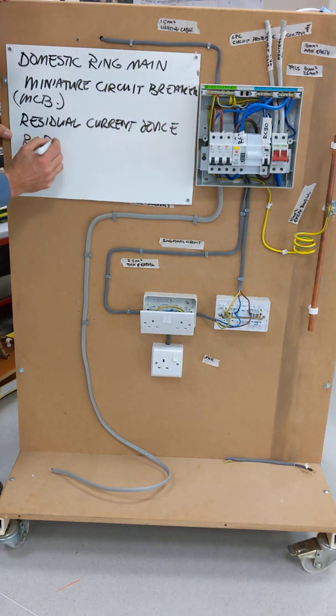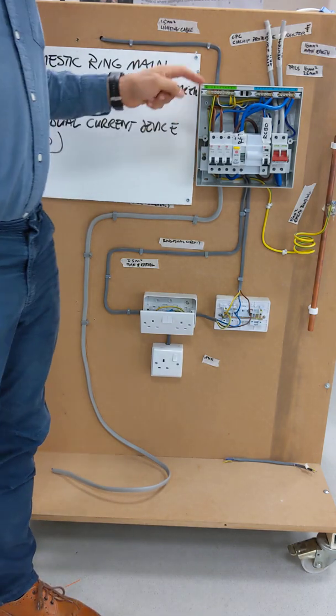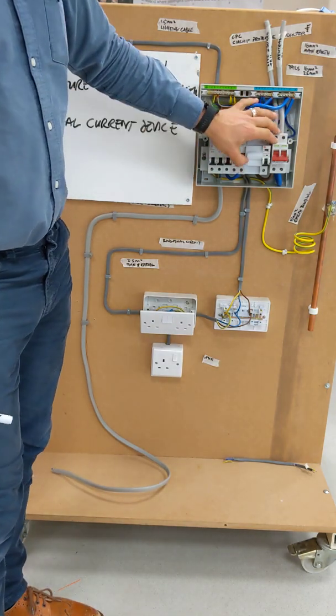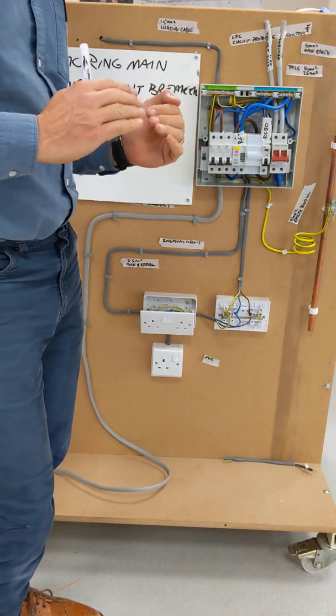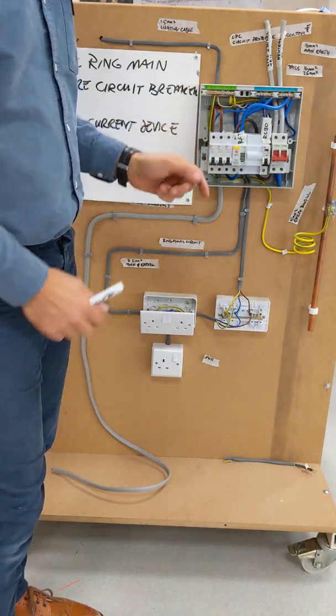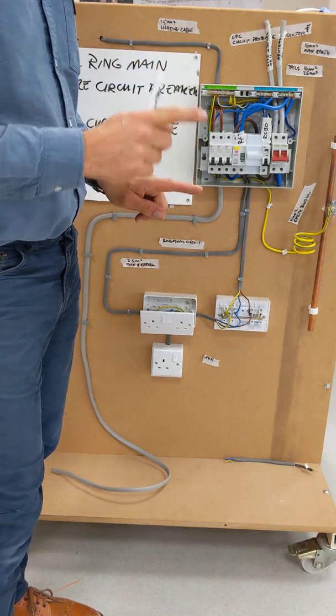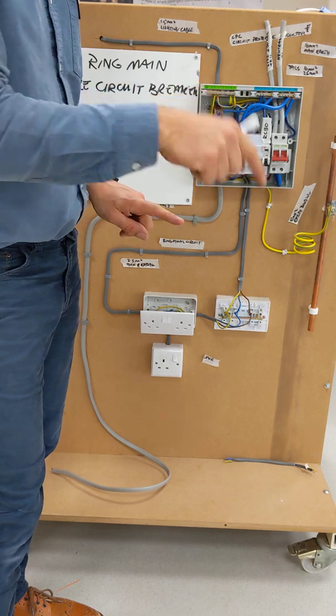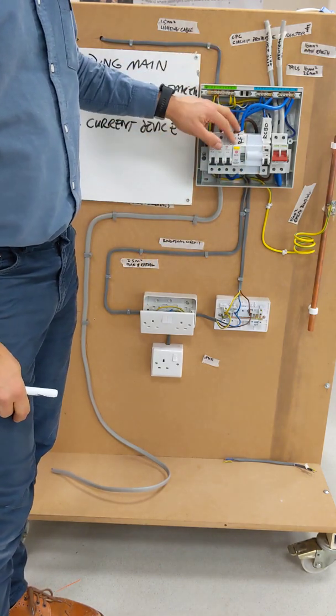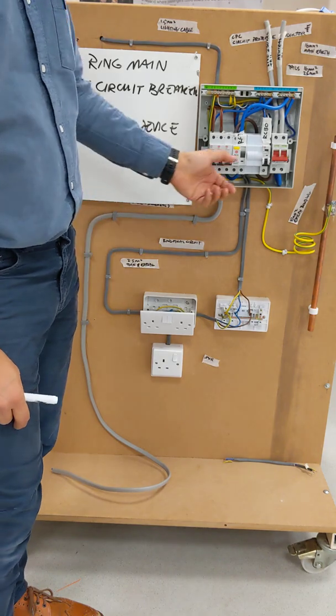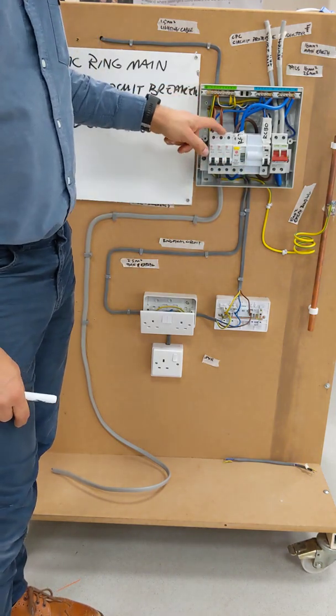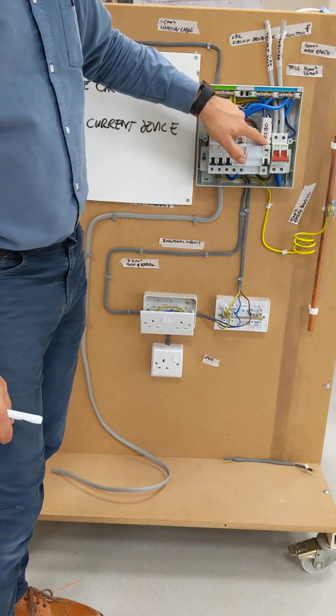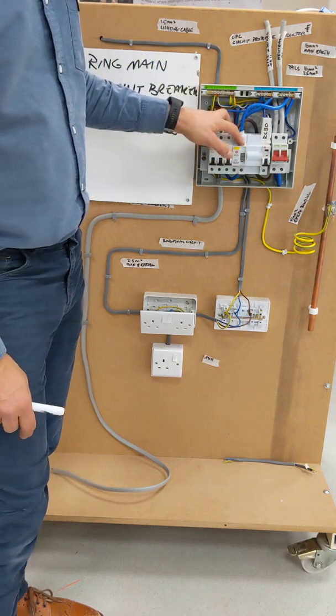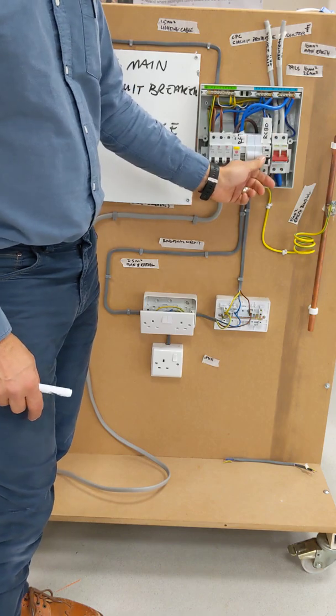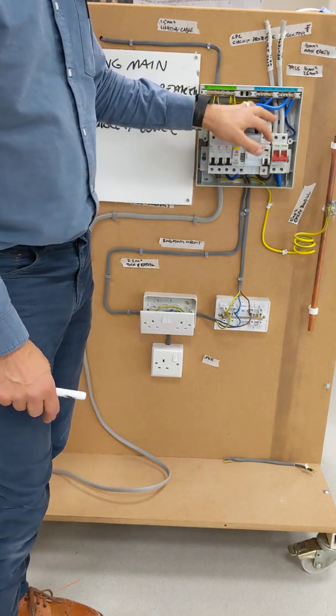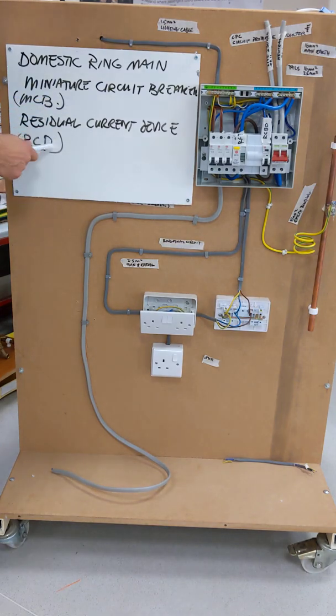RCD. Okay, so an RCD will trip at a much lower current and, basically, it detects an imbalance between current in certain parts of the circuit, either flowing between live and neutral, or neutral and earth, or live and earth, and it will detect an imbalance in the current and it will trip off at a very low current and it'll save you from having an electric shock. So MCB, RCD, and the last one we had, which is an RCBO, which is a combination of the two of them. So that one is often used in a circuit board instead of wiring the two together. So that's a combination of MCB and RCD.